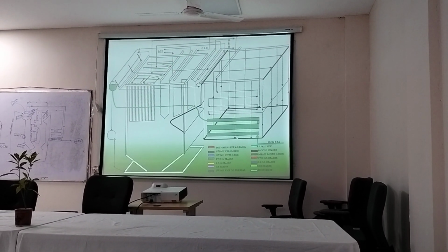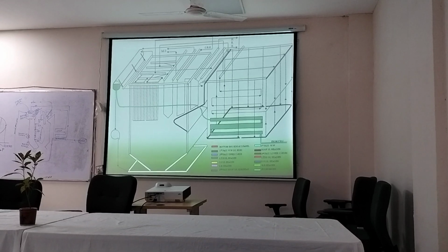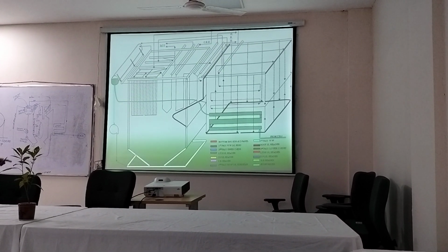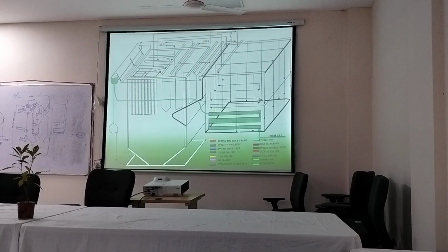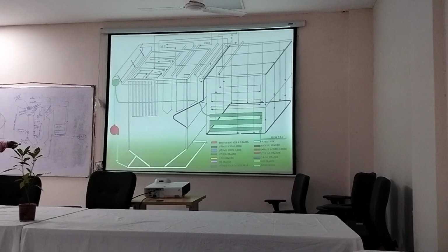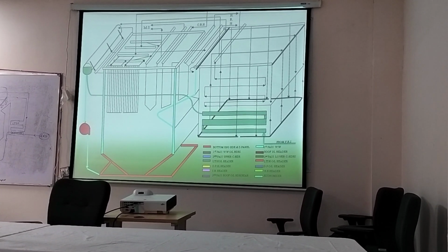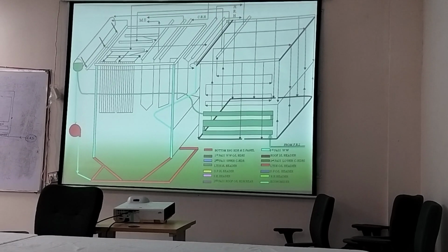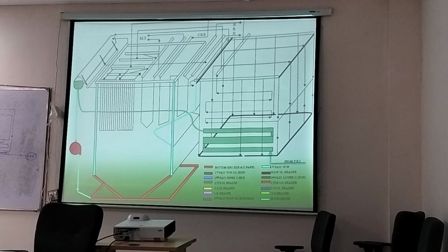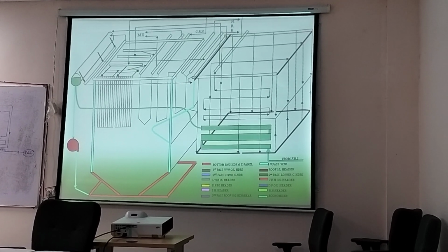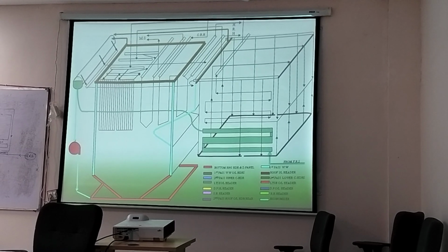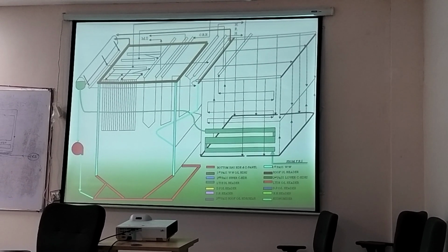Boiler drum. So you are sending to the boiler drum. From there, through downcomer tubes, the water is coming down, and there is a circulation pump as per requirement. You can run it. From there it is coming to the bottom header, and from there through the water wall, water is passing, and during that passage heat is added, and they are becoming a water-steam mixture. And this water-steam mixture is coming to the drum again.